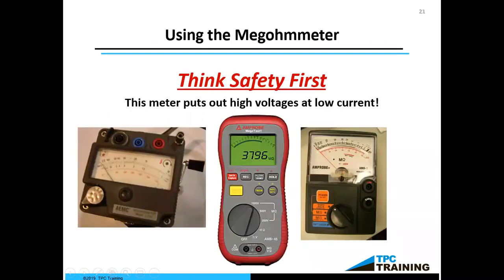So now I'm going to talk a little bit about the other check that we have to do on motors, and that is to check the quality of the insulation on those stator windings. So I've already talked about just checking if the winding is intact or checking if the winding is shorted. That's a very important step that we have to take. And also this step, which checks if the insulation is good or not. And so this is called megging out the windings.